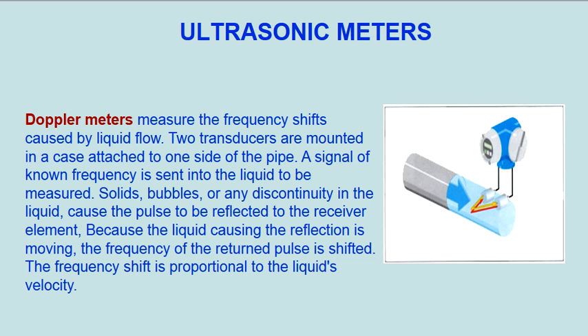A signal of known frequency is sent into the liquid to be measured. Solids, bubbles, or any discontinuity in the liquid cause the pulse to be reflected to the receiver element. Because the liquid causing the reflection is moving, the frequency of the returned pulse is shifted. The frequency shift is proportional to the liquid's velocity.